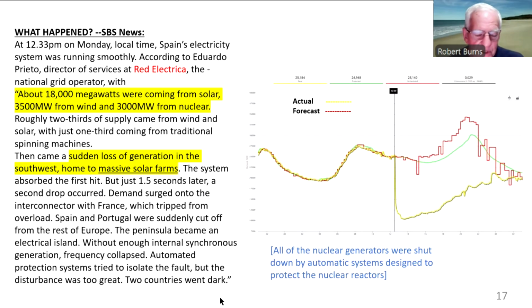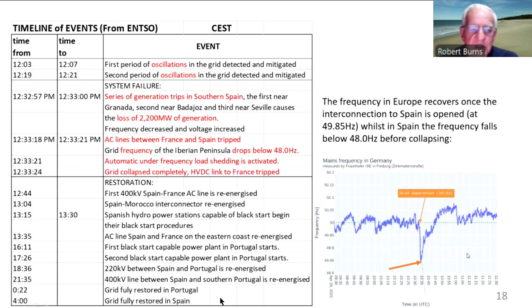Frequency collapse. Automatic under-frequency protection systems operated, trying to isolate the fault, but it was too big and it went black. The nuclears go into a shutdown mode designed to protect the reactors. So this is a little bit more detail about the actual sequence of events.